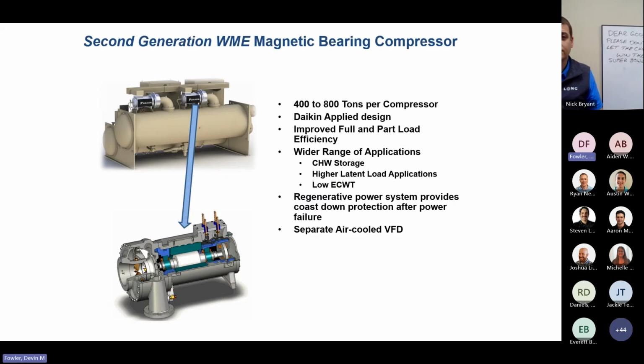Our WME chillers are on their second generation. With these, nothing's going to change between what we currently offer with WME and R134A or R513 compared to R515B. The only thing that is going to be different is our load is going to change a little bit. We're traditionally 400 to 800 tons per compressor with WME compressors. This is a Daikin Applied design. We design and build these in-house in our Stanton factory.